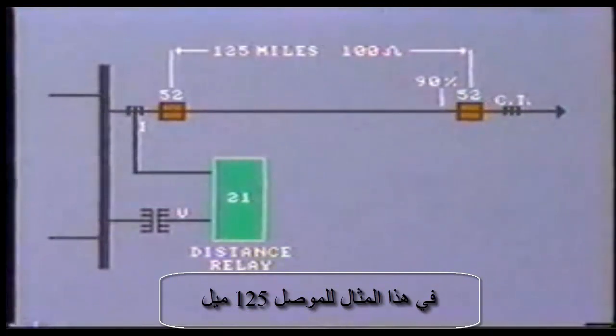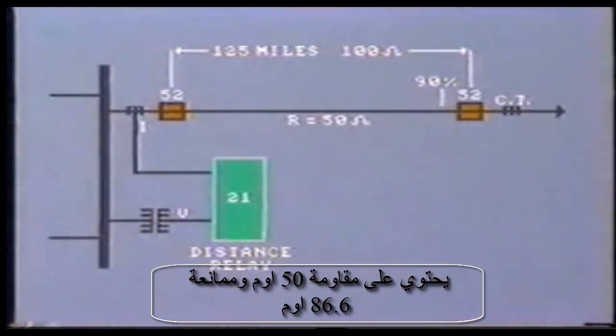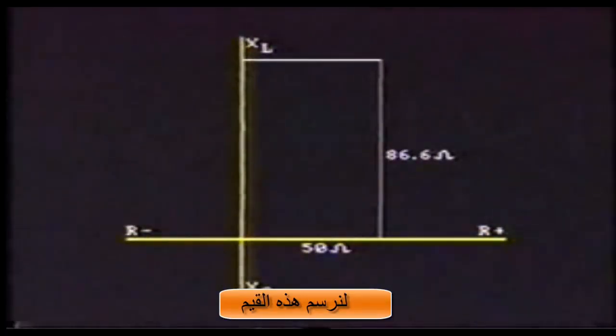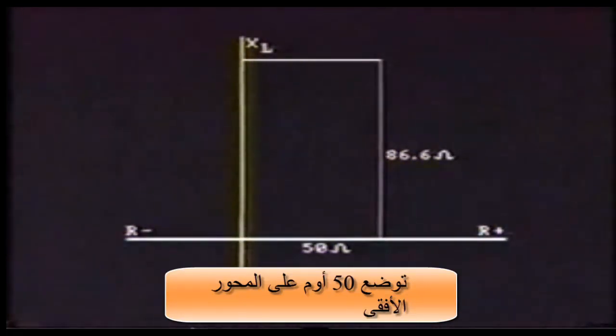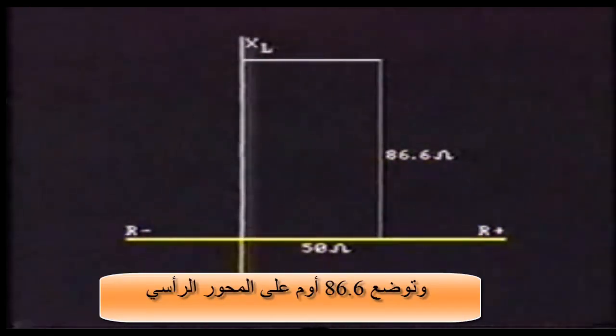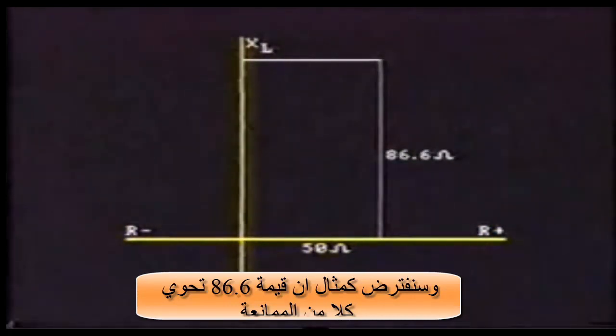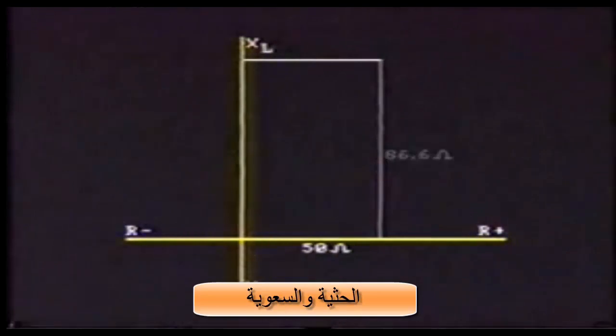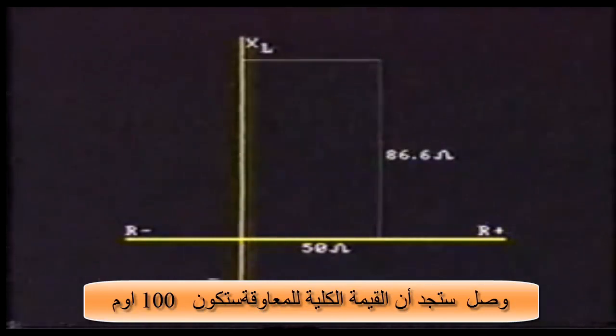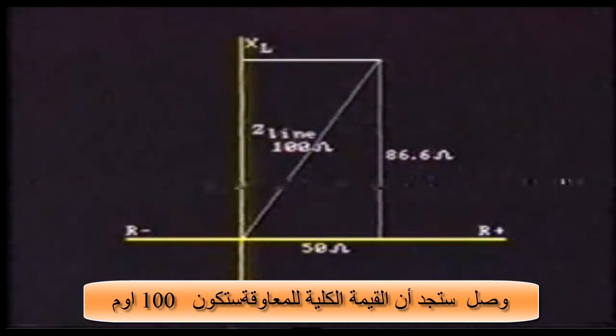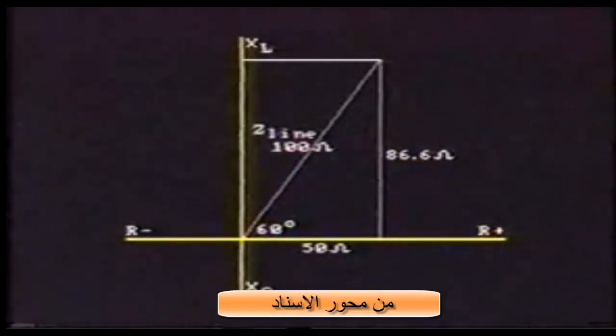It is important to note that we are talking about the impedance measured by the relay, not the resistance, because the conductors contain both resistance and reactance. Typically, the conductors in this 125-mile-long transmission line will contain a resistance of 50 ohms and reactance of 86.6 ohms. Let's plot this on an impedance diagram. Resistance is shown along the horizontal reference vector, and inductive reactance is shown on the vertical axis. Capacitive reactance, if present, would be shown on the negative vertical axis. In this example, we assume the quoted 86.6 ohms reactance has taken into account both inductive and capacitive reactance. Plotting resistance and reactance, we find that the total impedance comes to 100 ohms at an angle of 60 degrees from the reference vector.